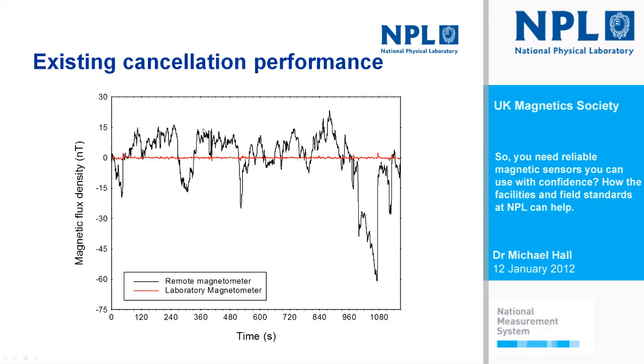But it is a significant improvement, and the origin of these variations in the ambient magnetic field is the electrified train system that we have here in the Teddington region, in this part of London. That system works by a third rail, which provides the power. That rail is insulated from the ground, but the return circuit is on one of the running rails, and because they're load bearing, they can't be insulated, and we get leakage currents into the ground. Those leakage currents, if you do your right hand grip rule, then generate magnetic field. The field that we see here in this graph is the vertical field, and that corresponds to the field direction for these leakage currents.